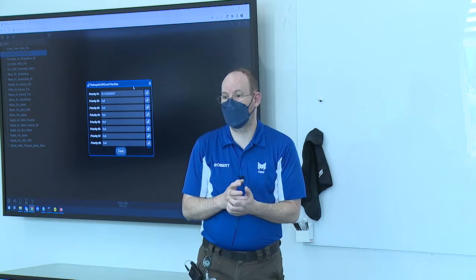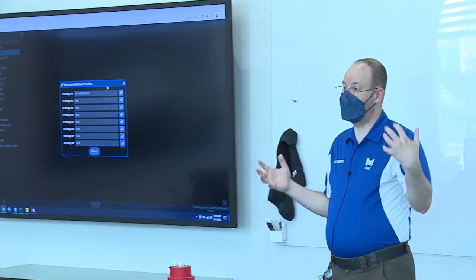Okay, I think I'll catch up. Some BACnet points by default are read-only, like that air handler 4 name that Ted asked about earlier. That is a read-only point. There is nothing that we can write in that, because it's literally data tied to that specific controller.